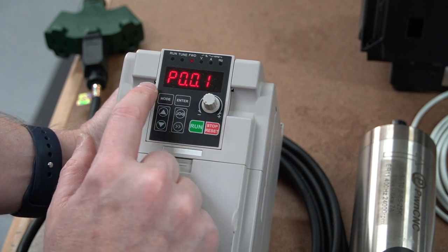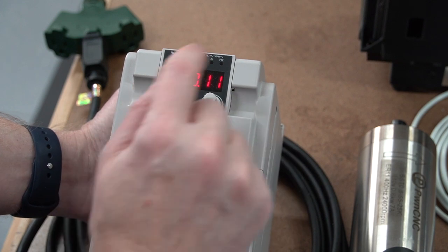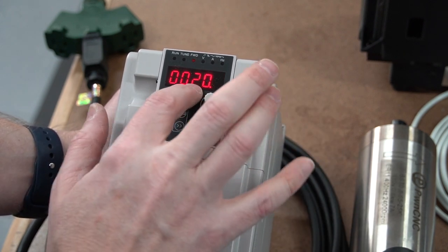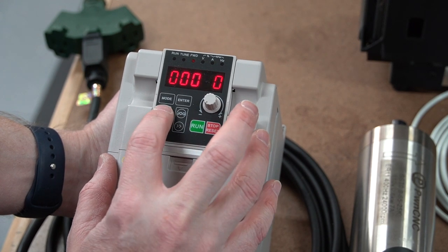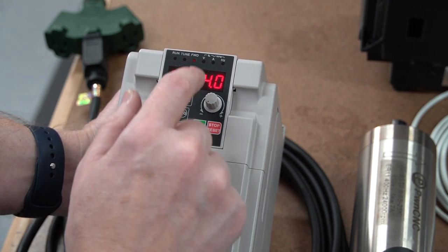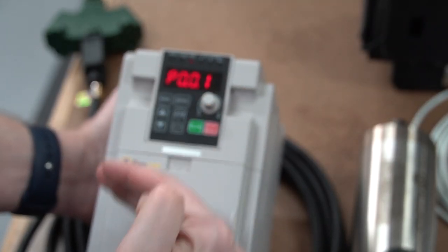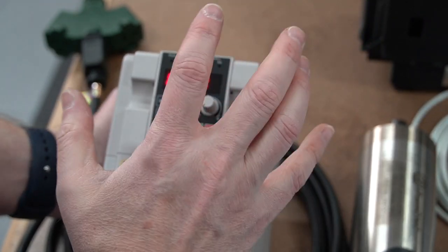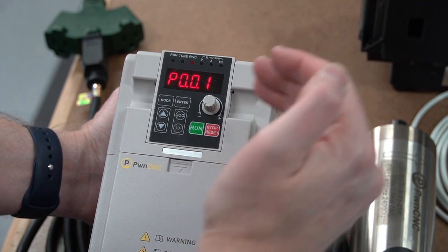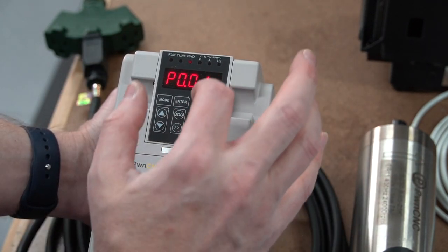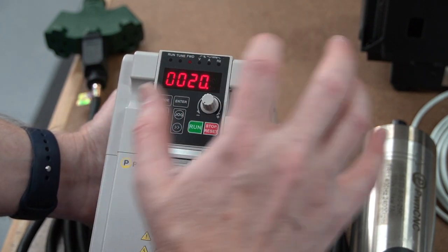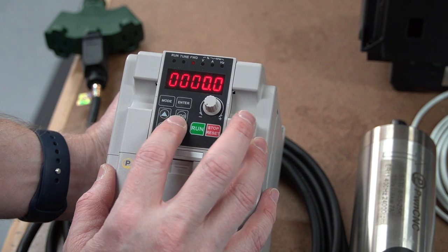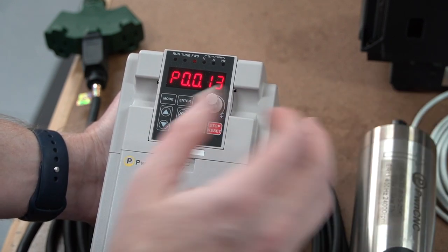So if we go to P0.0.11, hit enter. Right now it's set to 20 seconds. We need to change that to 4 seconds. So 0004.0, hit enter. And that's the acceleration, so whenever it goes from 0 RPMs up to your desired speed. This one relates to going from that higher speed down to 0 so that you can actually get in there and make bit changes. So we're going to hit enter, P0.0.12, and we're going to change this to a 4 as well. Enter.